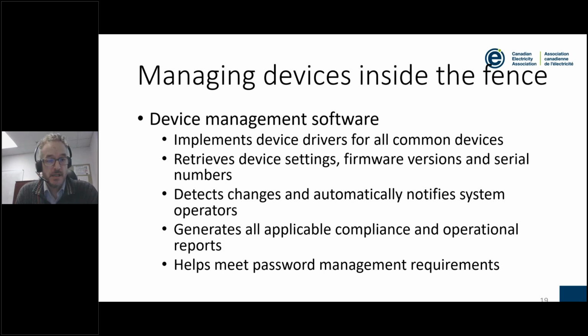Some key features: it'll retrieve the device settings, reading protection settings, network settings, whatever communication parameters are stored in the device. It will also retrieve information such as firmware version—not the firmware itself, since there's typically no use case for that, but just capturing what version it's currently running, whether it has any service packs or updates, as well as serial numbers. A typical management software keeps track of these settings and pieces of information, from a configuration, settings, firmware, and hardware point of view.